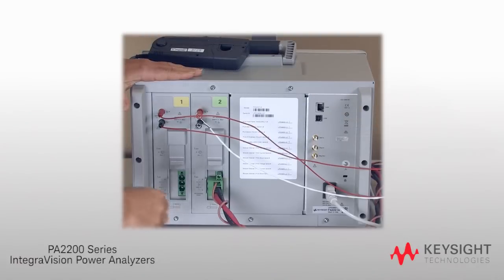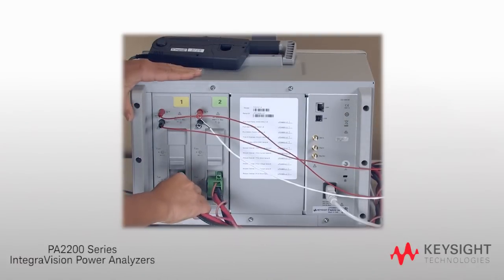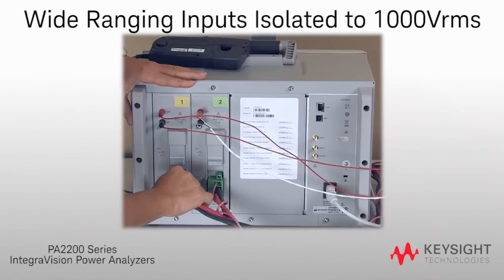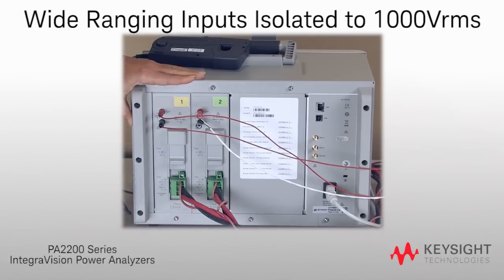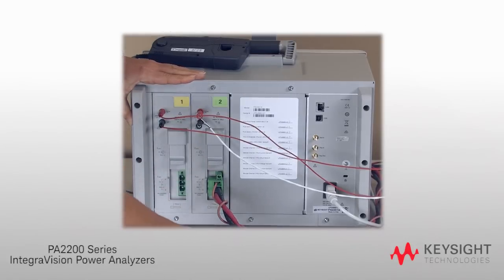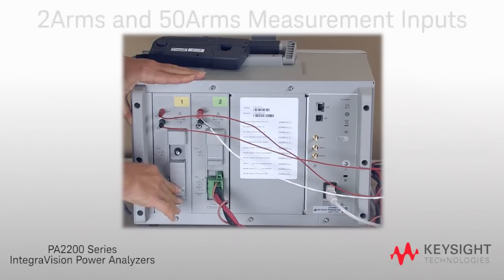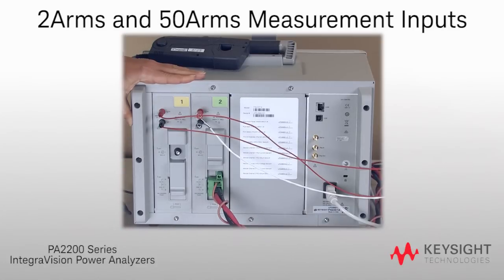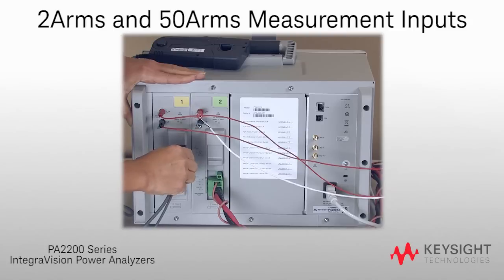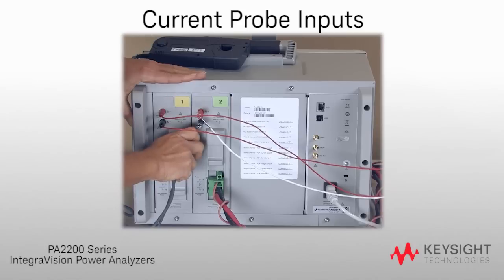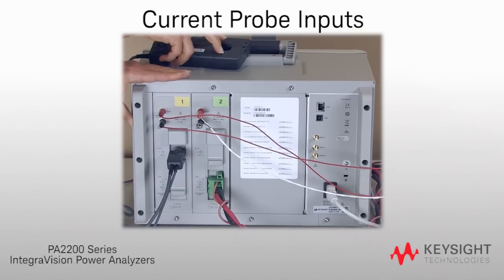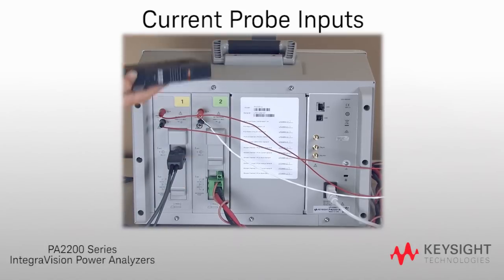With the IntegraVision Power Analyzer, you can address multiple test scenarios thanks to the flexibility of wide-ranging inputs that are isolated to 1000 volts RMS. To ensure the best accuracy, IntegraVision offers both 2 amp RMS and 50 amp RMS direct current measurement inputs, standard on all channels. It also has an external sensor input that supports current probes and transducers up to 10 volt full scale.